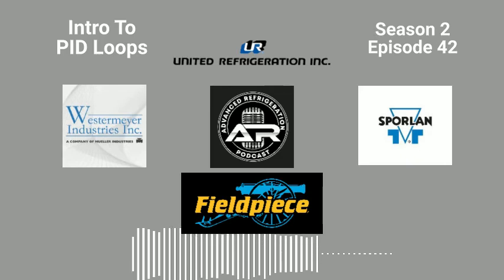Well, listen, let's just go through and state, because like I said, this is supposed to be an intro, right? So let's state some of the things that you would potentially tune. One would be electronic expansion valves, EPR tuning, especially if you're trying to control a pressure. A lot of times we're controlling the EPR based off of temperature, the average of the cases, which isn't really the best thing in the world. That never made any sense to me. If anything, I'd want to put a pressure transducer on there and have it cycle for that. If you have a lot of overshooting, that's when you start adjusting the PID loop.